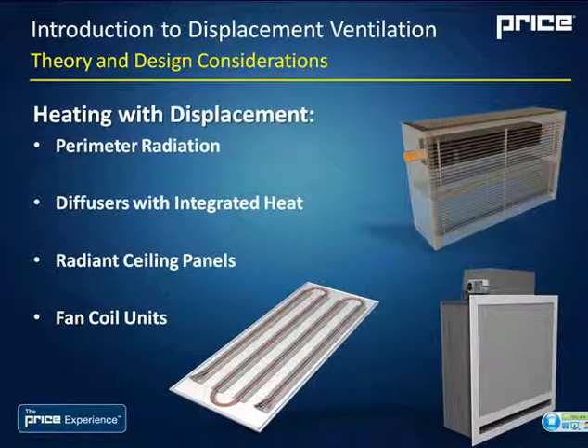There are a variety of different scenarios or different products that you can use or combine with a displacement system to provide heating. Systems that work well are things like perimeter radiation, so perimeter fin tube. We can combine diffusers with radiant heat and things like that. We have diffusers with integrated heat, which you see in the bottom right corner. There's a larger perforated face for the displacement operation and cooling. And then once it flips into heating, the actuator is going to close off one part of the plenum and direct the warm air through a slot diffuser.